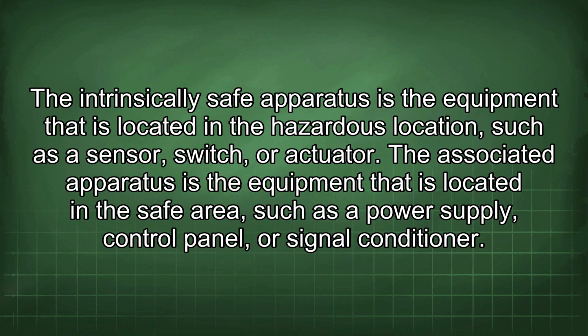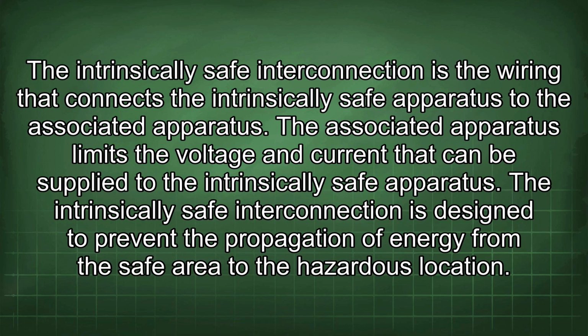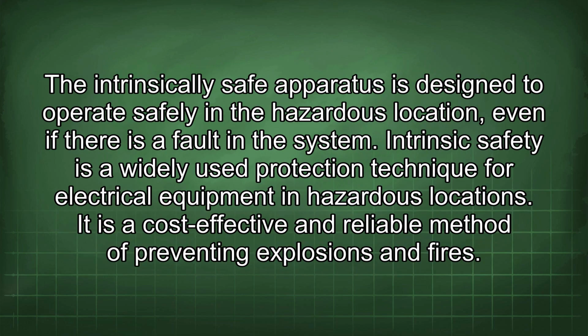The intrinsically safe apparatus is the equipment that is located in the hazardous location, such as a sensor, switch, or actuator. The associated apparatus is the equipment that is located in the safe area, such as a power supply, control panel, or signal conditioner. The intrinsically safe interconnection is the wiring that connects the intrinsically safe apparatus to the associated apparatus. The associated apparatus limits the voltage and current that can be supplied to the intrinsically safe apparatus. The intrinsically safe interconnection is designed to prevent the propagation of energy from the safe area to the hazardous location. The intrinsically safe apparatus is designed to operate safely in the hazardous location, even if there is a fault in the system. Intrinsic safety is a widely used protection technique for electrical equipment in hazardous locations. It is a cost-effective and reliable method of preventing explosions and fires.